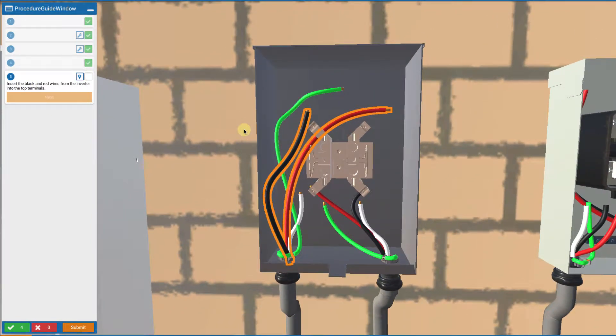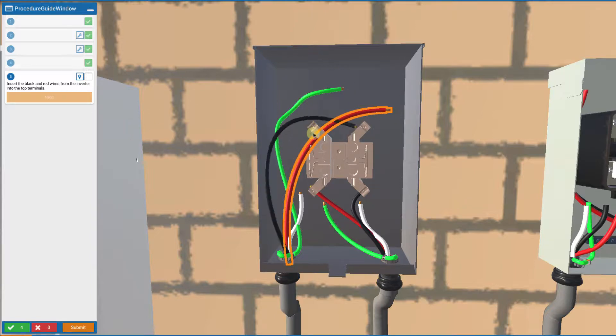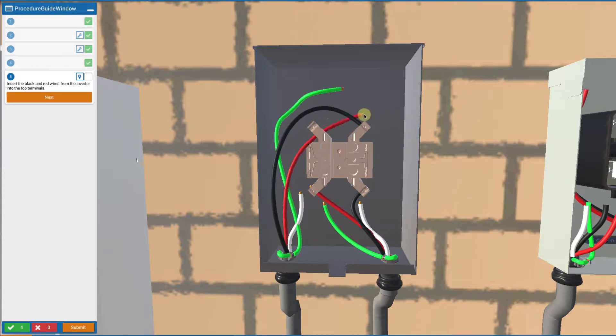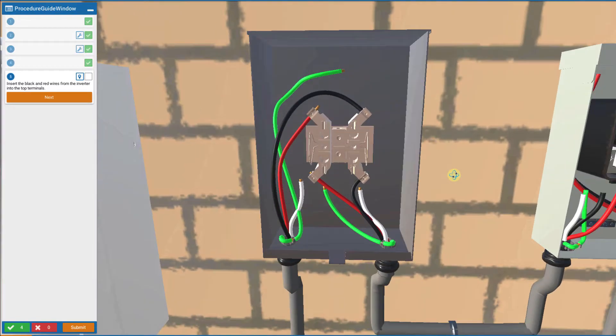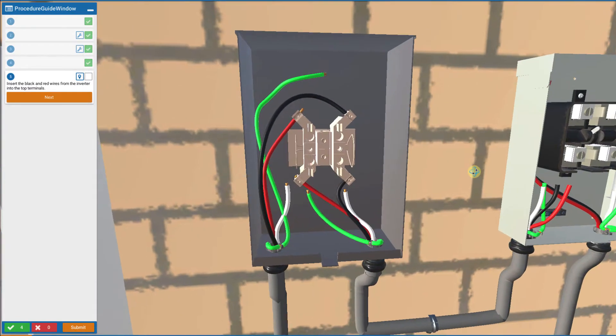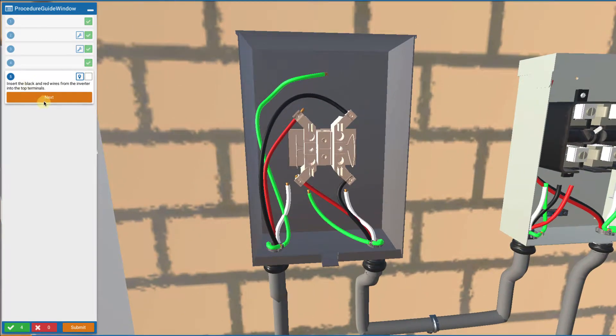Then we're going to touch on and insert the wires that are coming from the inverter into the revenue grade meter, and we want those to be on the top. So we're going to touch those wires and insert those into the two lugs on the top.